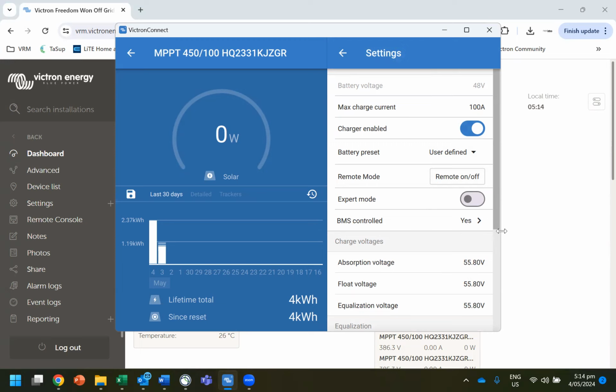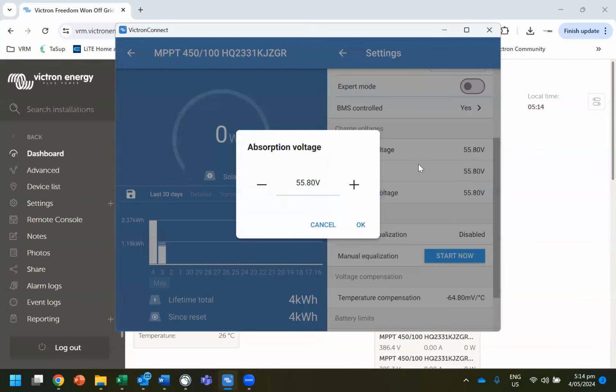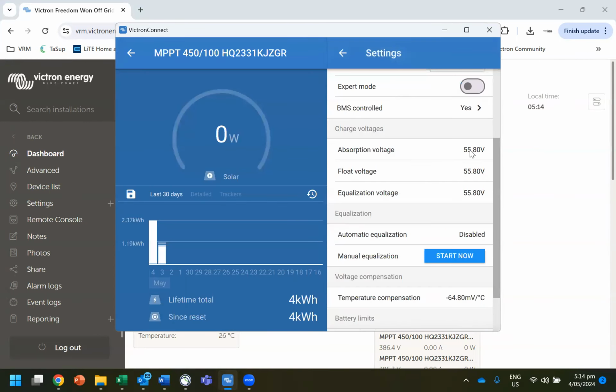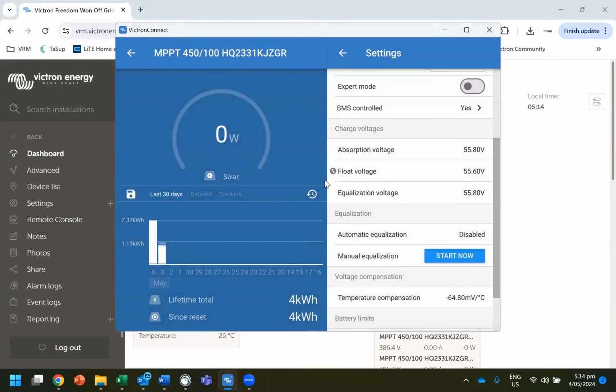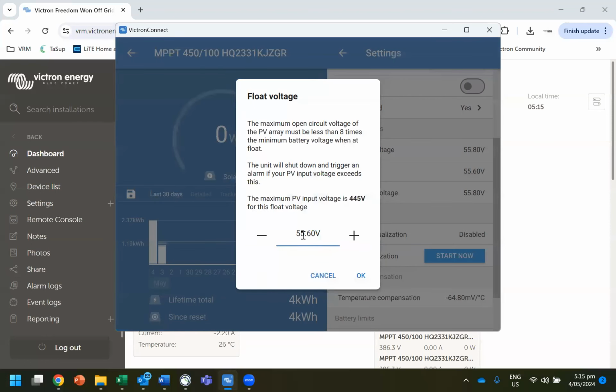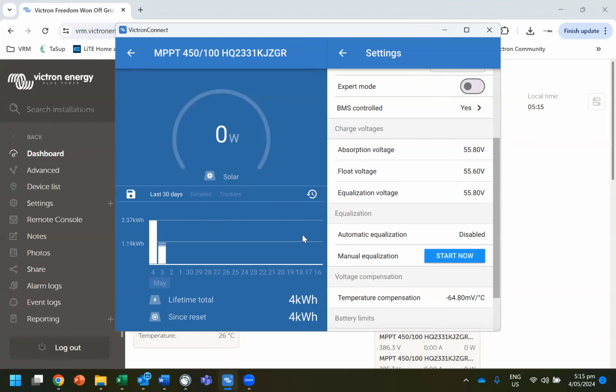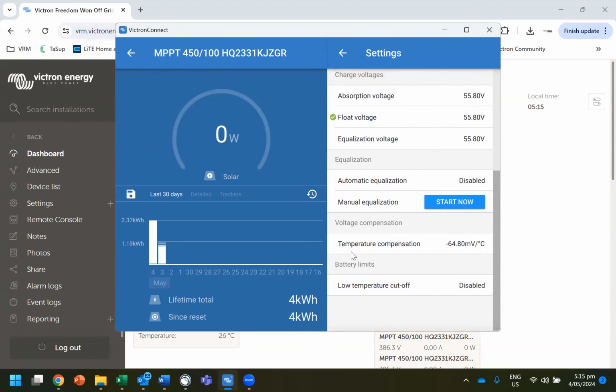So when it's not BMS controlled, the charge controller is going to use these settings. Whatever you set in here, the charge controller is going to use. Now, just for a demonstration, I'm going to change the float voltage to 55.6 and click OK. Now you watch. See here, this little green tick comes up. That means that setting has been put into the charge controller and it's done. You're programmed for that setting. So when you change something, you need to then set it up properly. So I'm going to go 55.8, and you need to set all of these at 55.8.